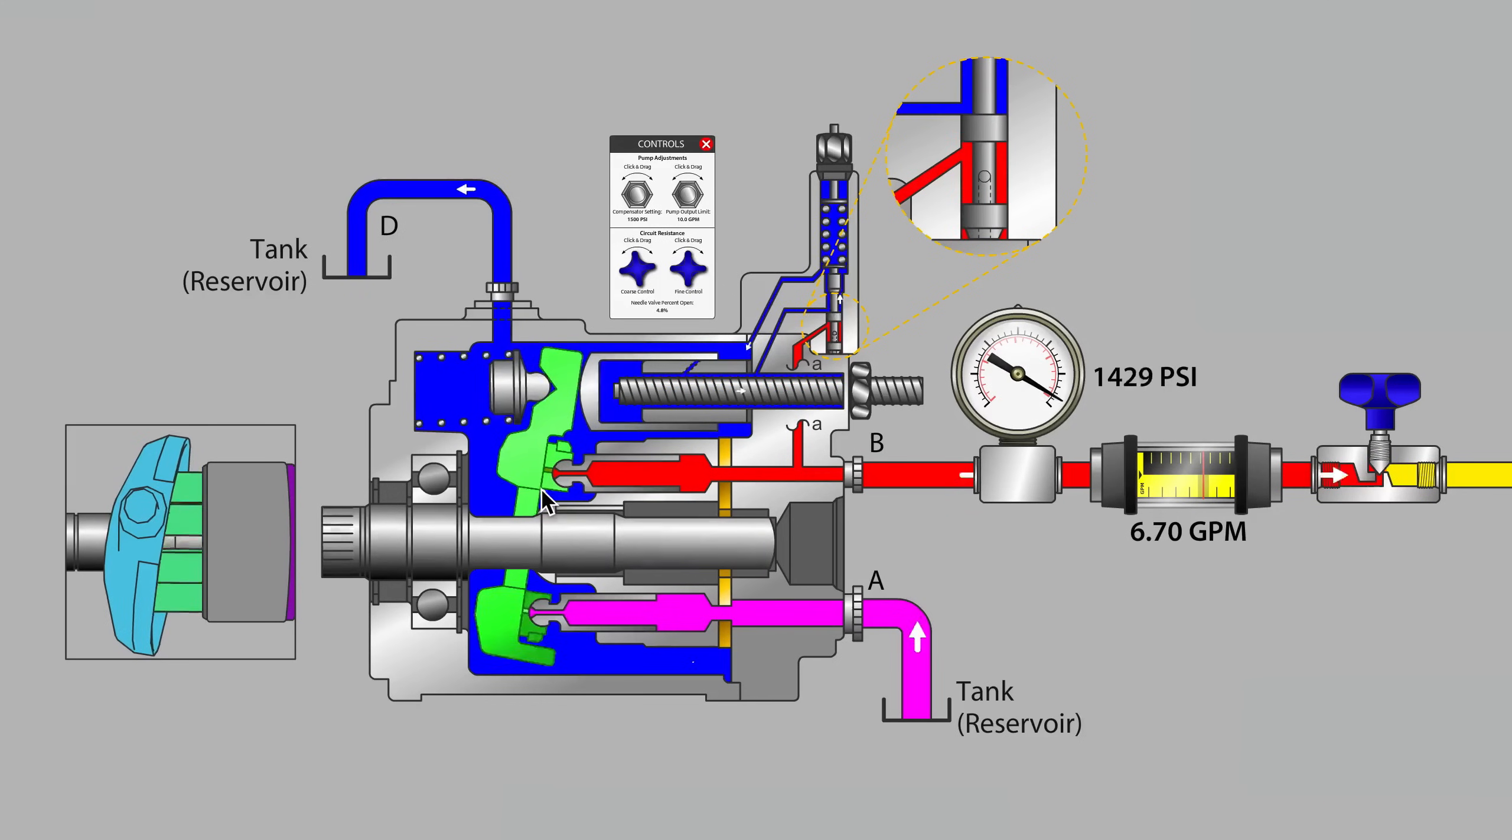We're lubricating the back of the slipper pad against the swash plate. We're lubricating the piston ball as it is socketed into that slipper pad or piston shoe. We are lubricating as well the cylinder barrel against the porting plate.